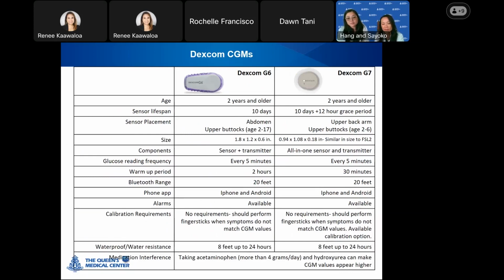And then here's a layout of the Dexcom systems. So we have the Dexcom G6, and then we have the Dexcom G7. The Dexcom G6 and G7 are both indicated in 2 years and up. The sensor lifespan of the G6 is 10 days. For the G7, it's 10 days plus a 12-hour grace period. The sensor placement is indicated in the abdomen for the G6, or upper buttocks for ages 2 through 17. For the G7, it's the upper back arm, or the upper buttocks for ages 2 through 6. The size is a little more than 1.5 inches, close to 2 inches, for the G6, and closer to about 1 inch for the Dexcom G7, similar in size to the Freestyle Libre 2.